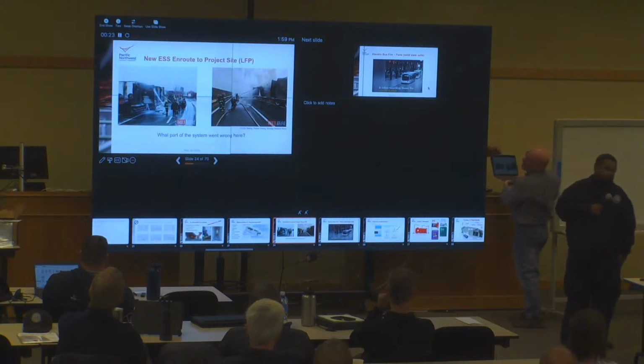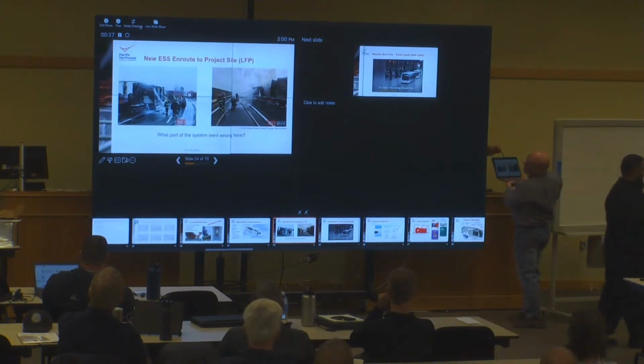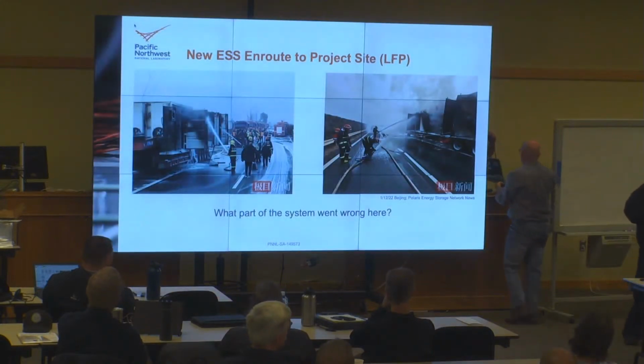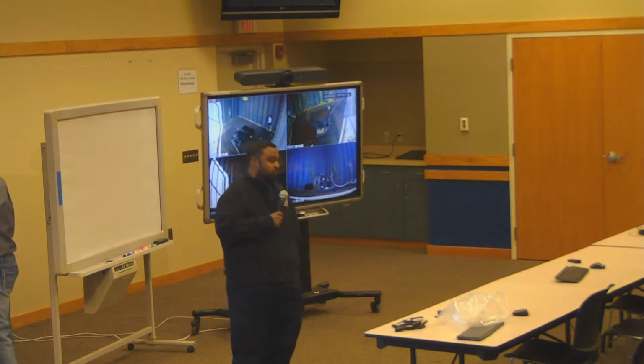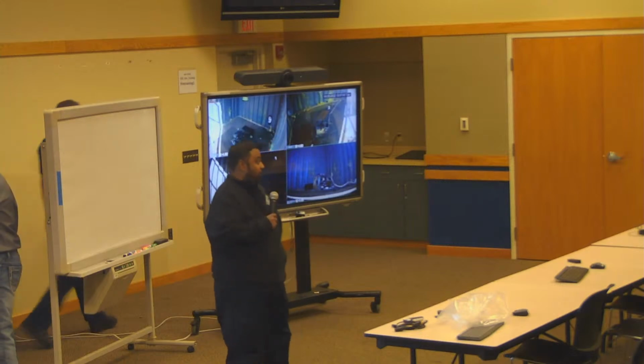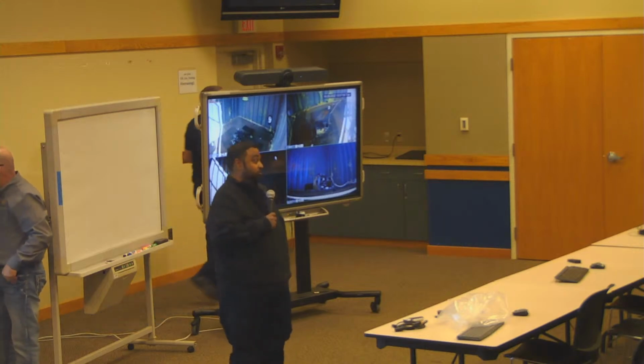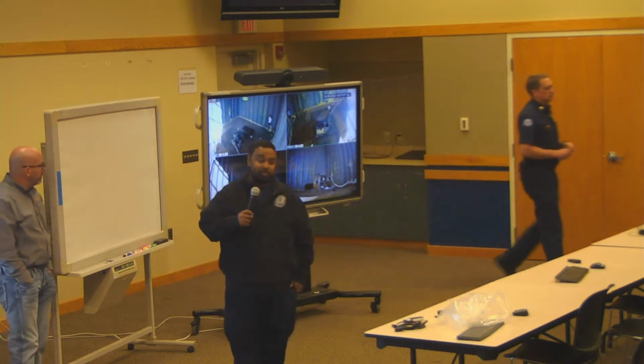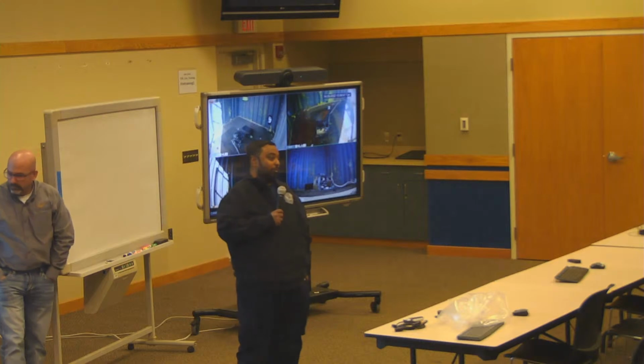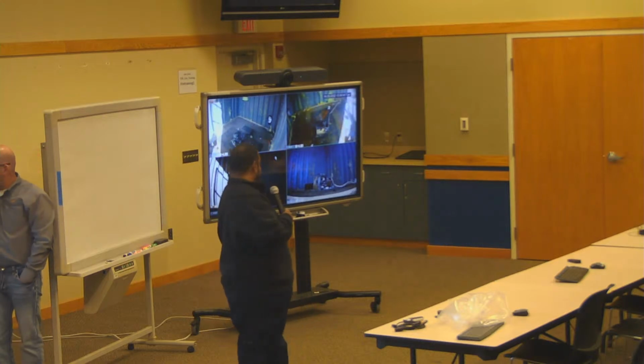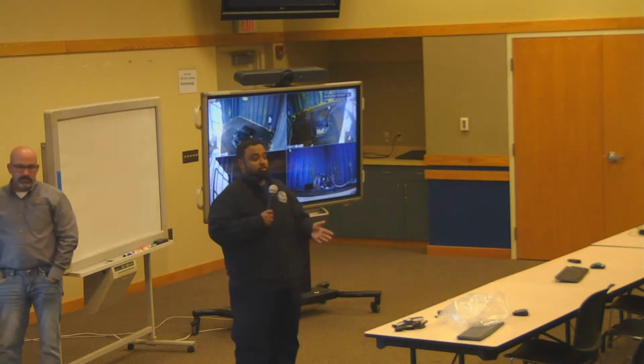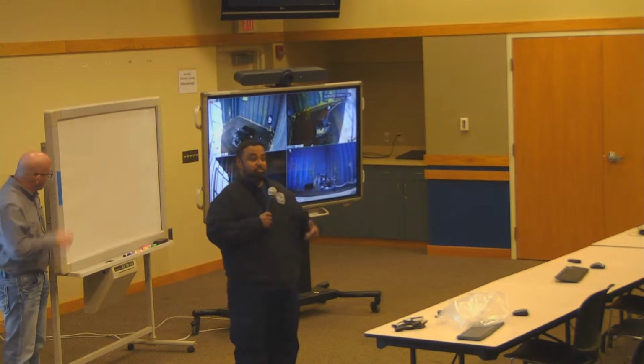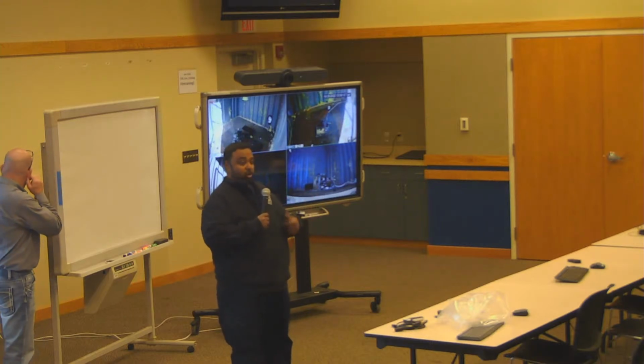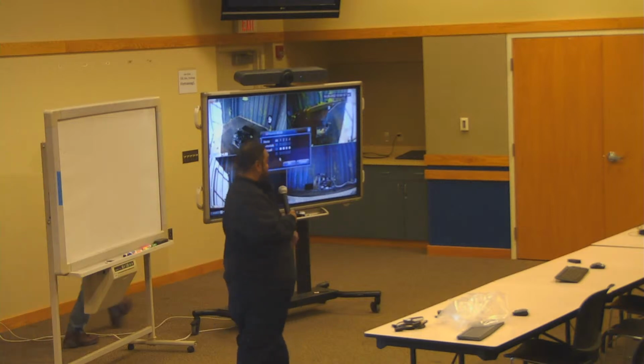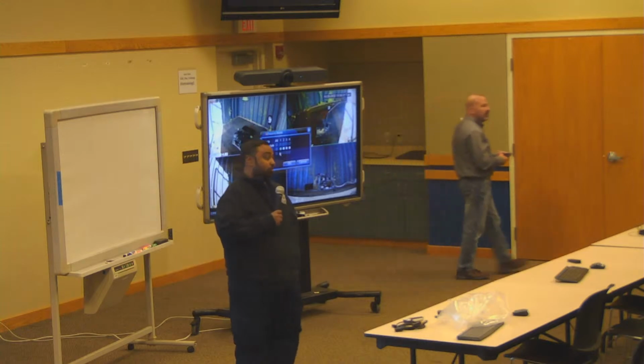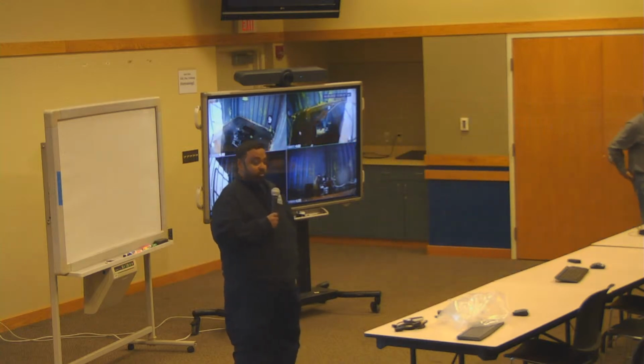How's it going, guys? So we set off that first one like we were talking about, where we had the cartridge heater inside with some lithium batteries. As you can see, there were early on 4 distinct kind of explosion events. Those were the 18650s in the immediate vicinity of the cartridge heater. This box, like the one you see up here that you can look at during the break, is rated with some fire resistance associated with the blanket within it to prevent flame and fire propagation out of it once the failure occurs. But that looks like a burned up box in a pile to me. We killed the cartridge heater as soon as the first batteries popped. So at that point, it was just the batteries propagating and then the flaming impingement upon the cardboard, allowing it to continue to burn. So this is basically the scenario of an energized battery that was disposed of in transit with one of these boxes, going into thermal runaway and the subsequent fire that you see.